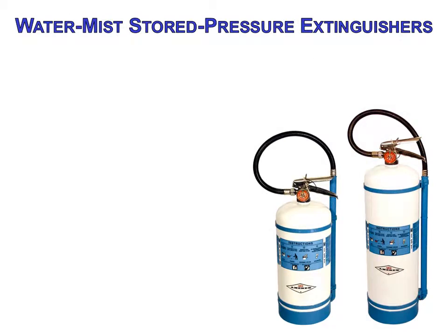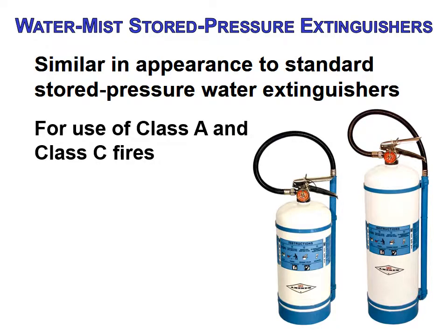Water mist stored pressure extinguishers are similar in appearance to standard stored pressure water extinguishers, for use on Class A and Class C fires. They use deionized water and a nozzle which produces a fine mist, making them suitable to use on energized electrical equipment.